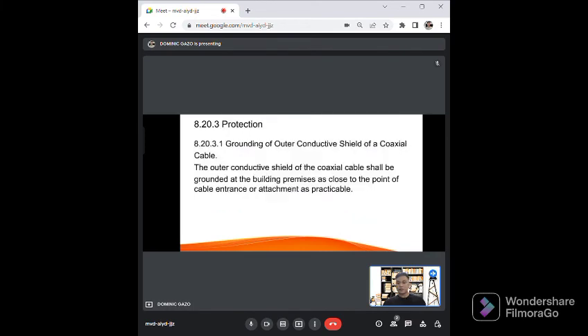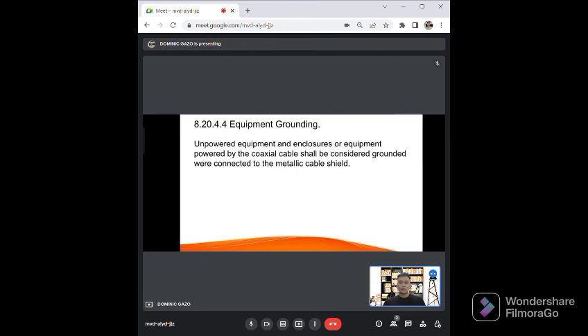For the protection, grounding outer conductor shield, the outer shield shall be grounded at the building premises as close to the point of cable entrance or attachment as practicable. For equipment grounding, unpowered equipment and enclosures of equipment powered by coaxial cable shall be considered grounded where connected to the metallic shield.